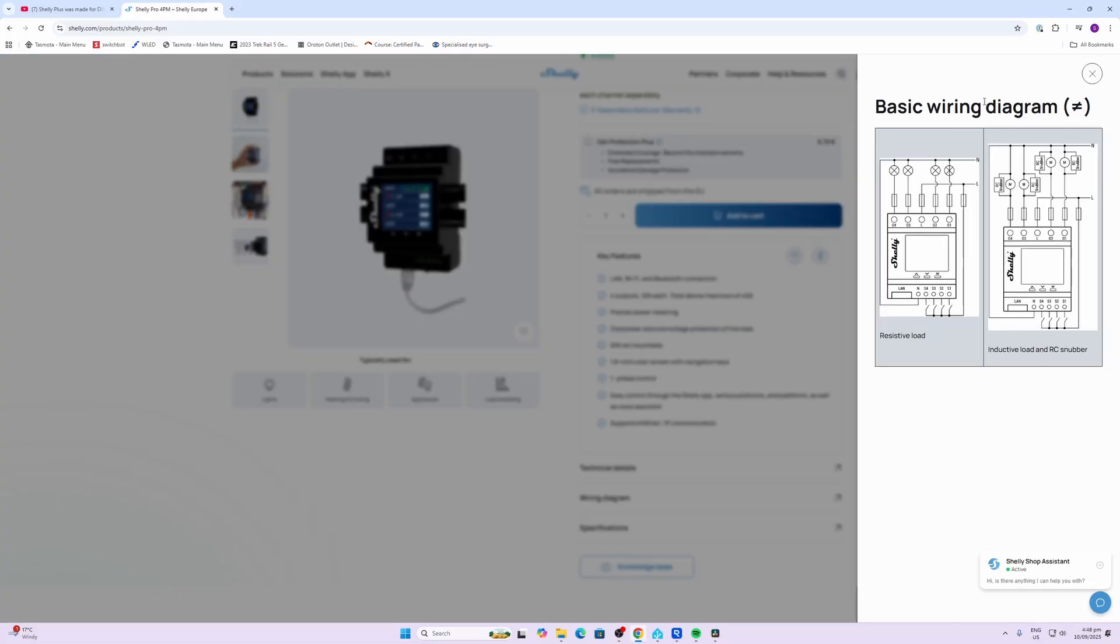Wiring for this device requires a neutral coming in over here, your live coming in over here, and then you've got the outputs one through four which will be powering your lights or whatever other load you're using, and then on this side you've got your switches connecting back to live.